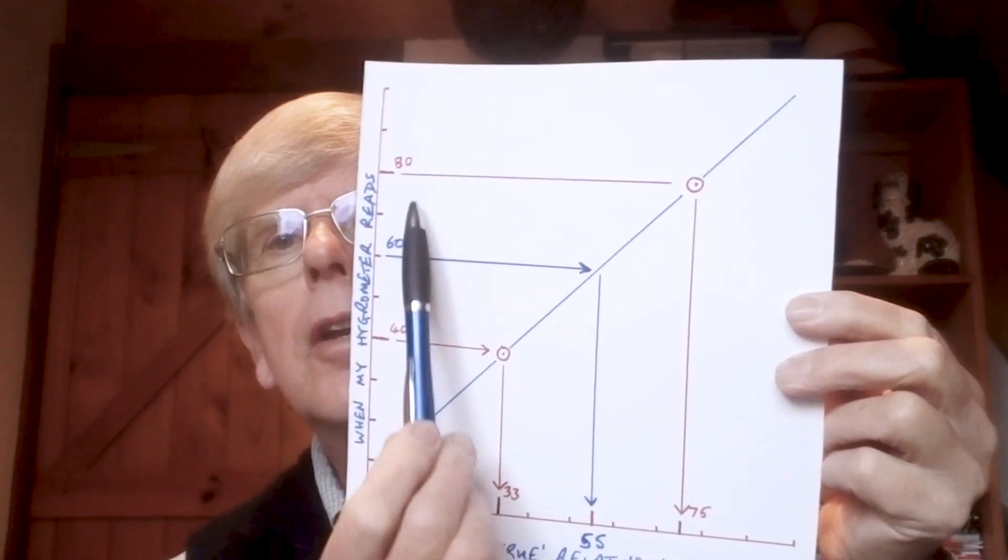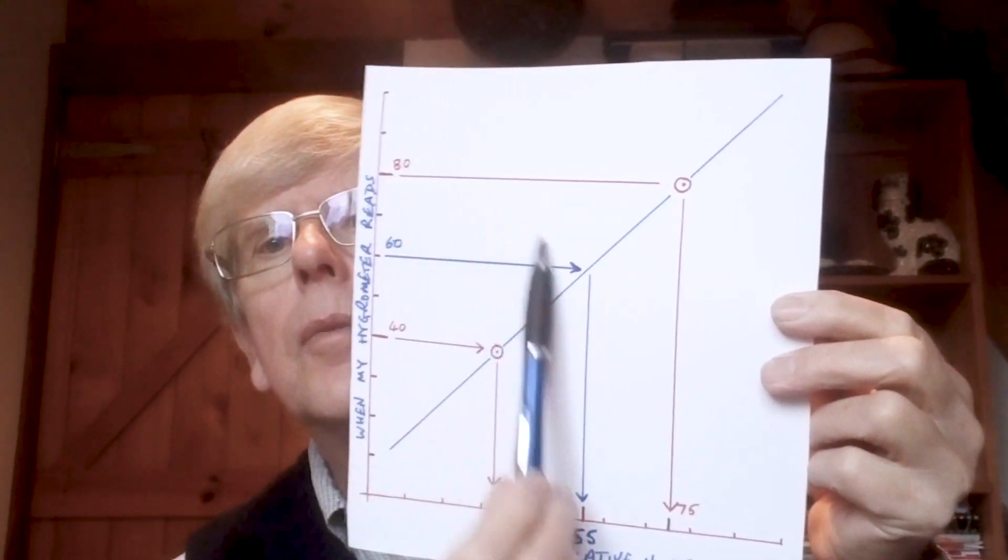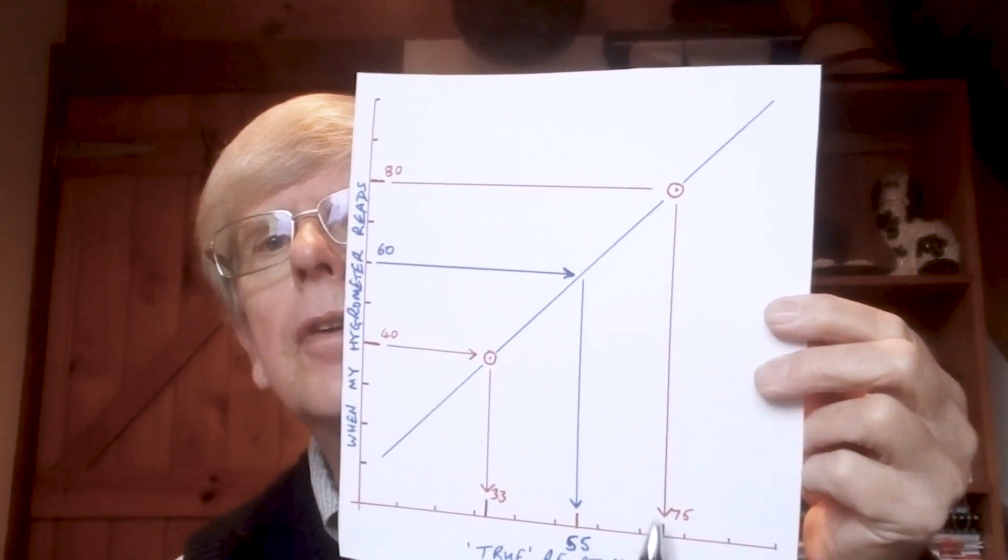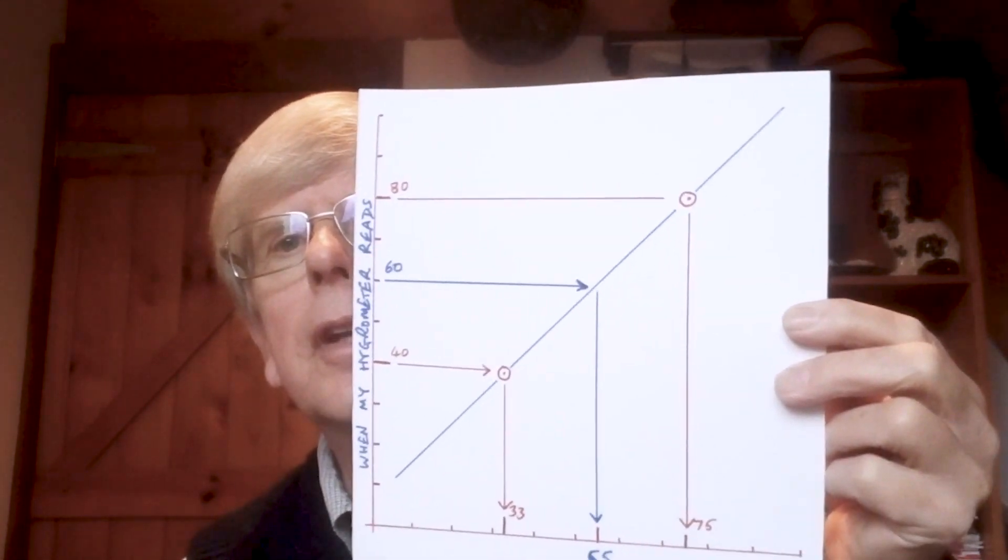And then you do the same again using the salt, and you read 80, and it should really read 75. So you've got another point, and then you draw a conventional calibration line as shown there in the blue.